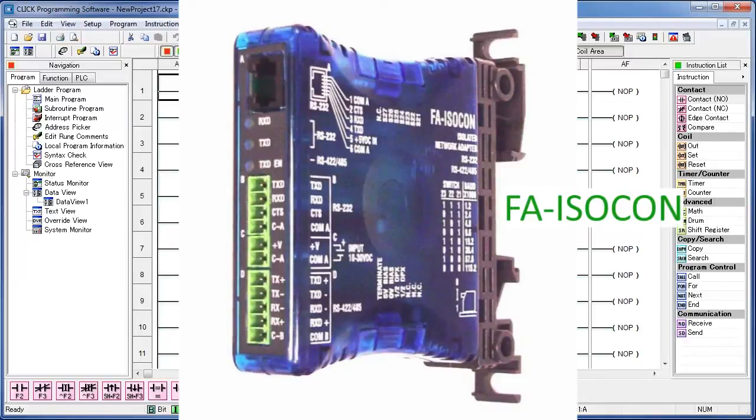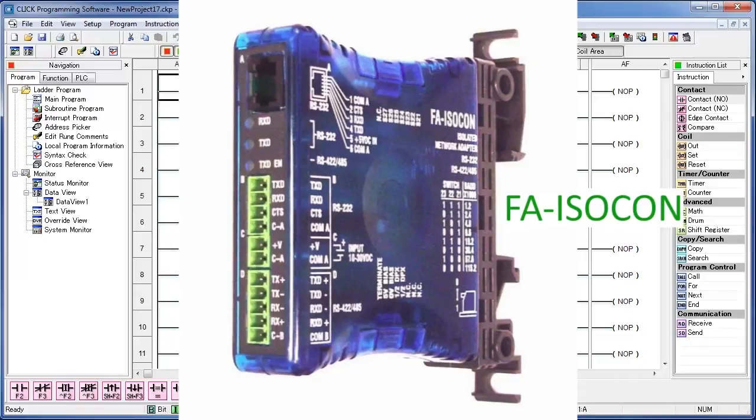you can use a converter that converts RS-485 to RS-232, which you can then plug into port 2 on your PLC. You can find a converter on the AutomationDirect website using part number FA-ISOCON.